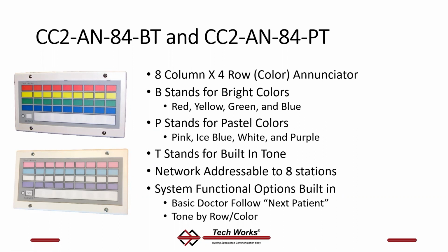You can also set tone by row in this family of product. Again, this is one of those differentiators between nurse call and clinic call. In a nurse call, you want every light to tone. In a clinic, you don't. You might just want the red to have a tone and the other colors no tone. What we used to call our old quiet firmware in the older version of this product.